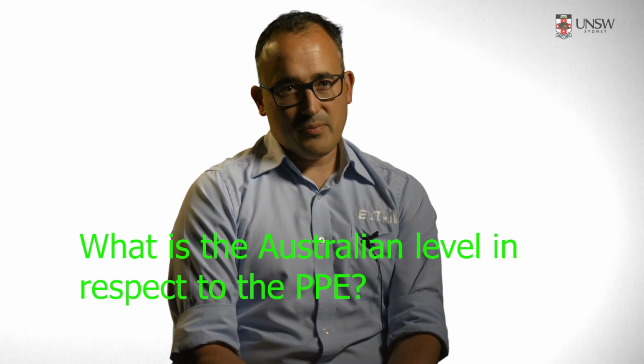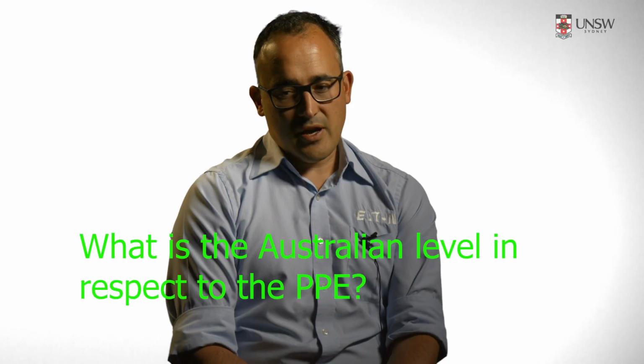But generally, with the PPE level, we look at the energy potential within the arc flash itself. Incident energy, and that's placed into categories. So we have category 1, 2, etc. From there, the PPE equipment has a CAL rating, and we use that CAL rating to then assess what PPE the person should be wearing.